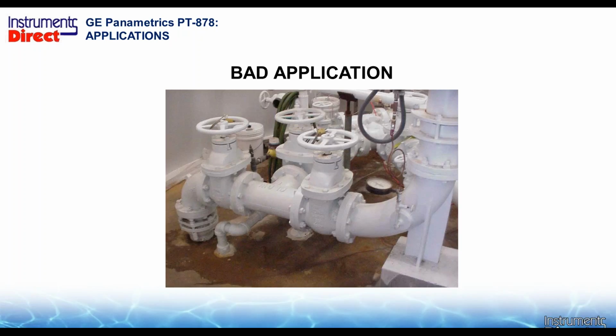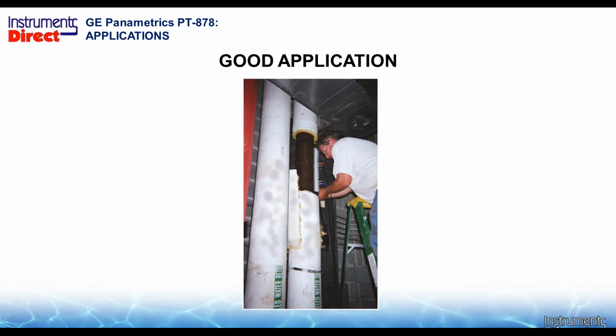So we need to measure flow in this application. No problem. Go upstream, go downstream. If you have an application that's important enough, someone may have to get the backhoe out and dig a hole to get to your straight run of pipe. So rule of thumb is, if you've got a long flow survey, a long distance, a lot of effort to get there, talk about the plumbing or the flow hydraulics before you get to the site. It can save you a lot of time, and you won't have to take the lumps when you get there.